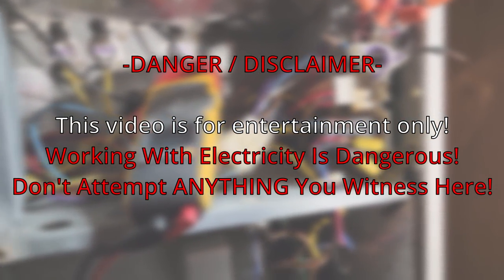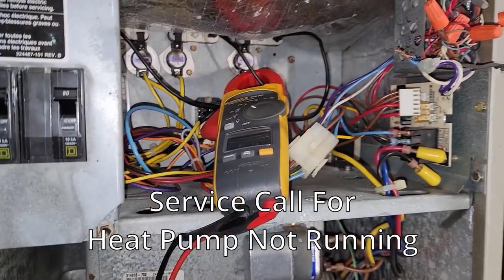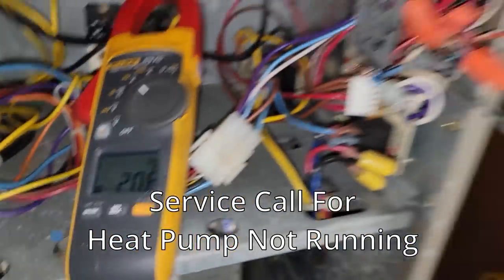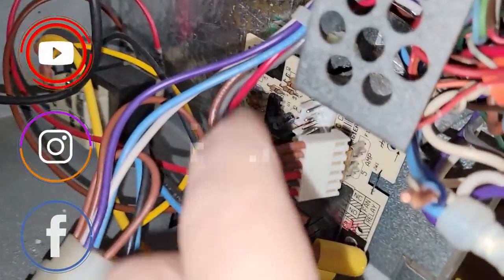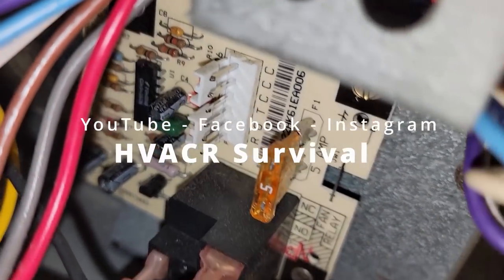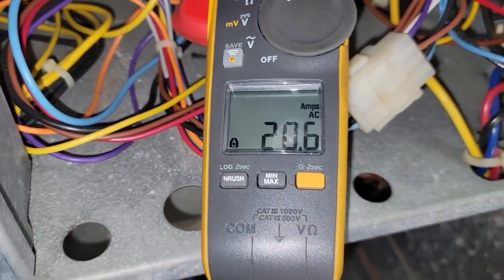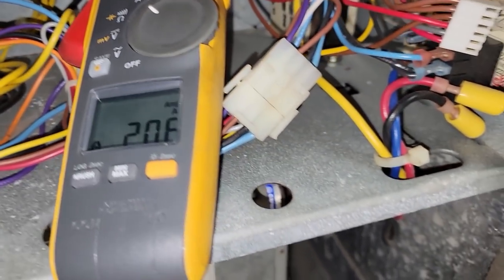We went upstairs to check the wiring on the thermostat - just a generic Honeywell - then came down here and noticed one of the elements was on. I ended up unplugging the thermostat wires from the control board - that's the easiest thing to do. We undid R, G, W, Y and all that, and it's still running, meaning we're still pulling the amperage on our relay and it's sticking on.